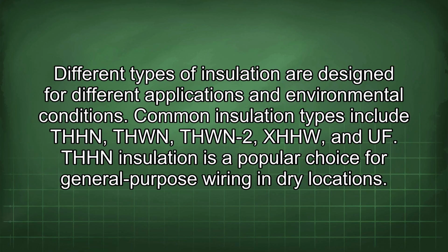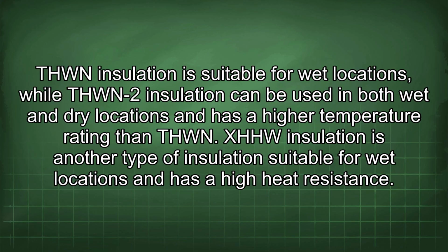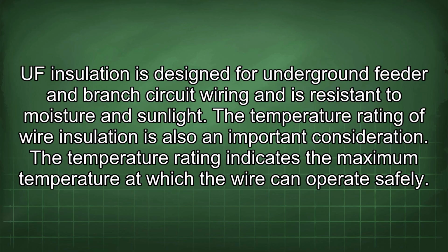Different types of insulation are designed for different applications and environmental conditions. Common insulation types include THHN, THWN, THWN-2, XHHW, and UF. THHN insulation is a popular choice for general-purpose wiring in dry locations. THWN insulation is suitable for wet locations, while THWN-2 insulation can be used in both wet and dry locations and has a higher temperature rating than THWN. XHHW insulation is another type of insulation suitable for wet locations and has a high heat resistance. UF insulation is designed for underground feeder and branch circuit wiring and is resistant to moisture and sunlight.